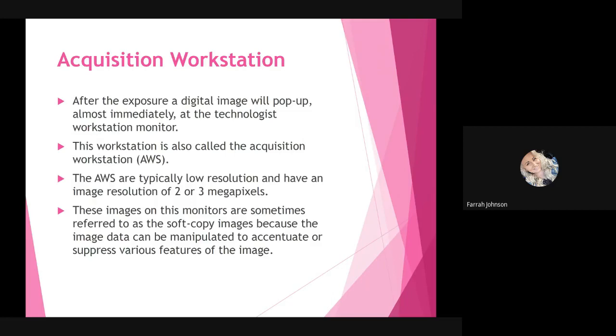Then that brings us to your acquisition workstation. So after the exposure, a digital image will pop up almost immediately at the technologist workstation monitor. This workstation is also called the acquisition workstation. Those workstations are typically low resolution and have an image resolution of 2 or 3 megapixels. The images on these monitors are sometimes referred to as soft copy images because the image data can be manipulated to accentuate or suppress various features of the image. Okay, so same thing as in X-ray, this is where our images pop up, that we can make notations, we can window level. That is all on the technologist acquisition workstation.